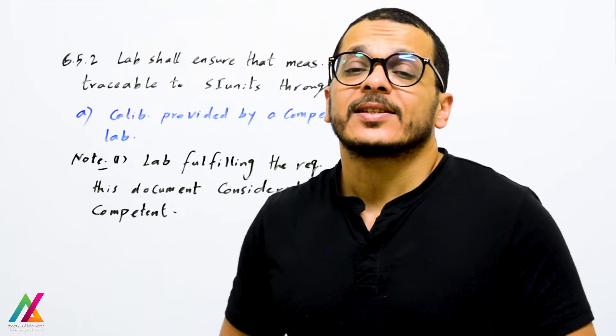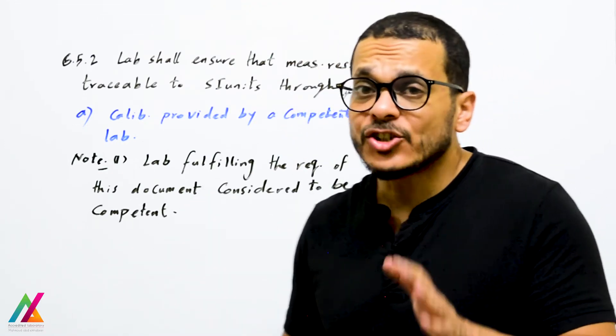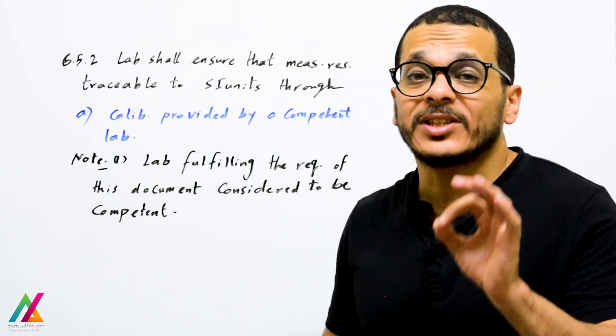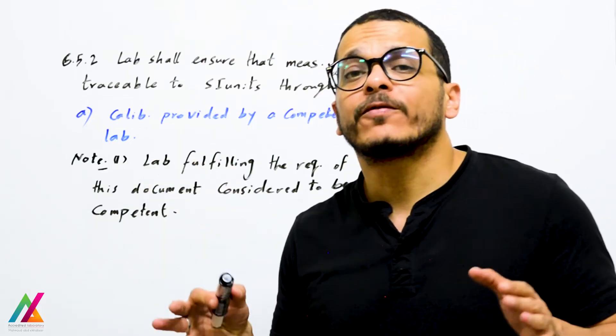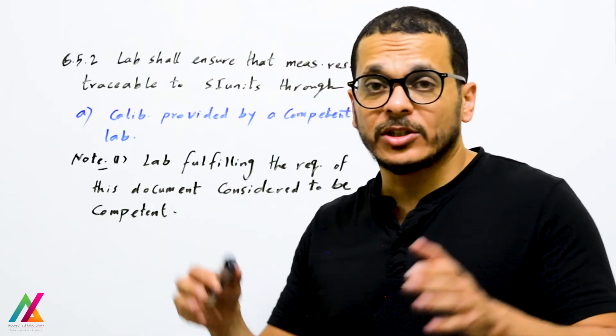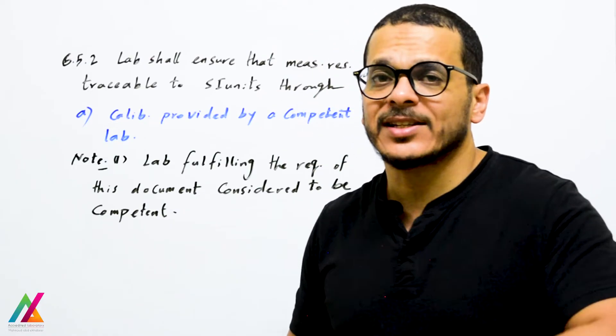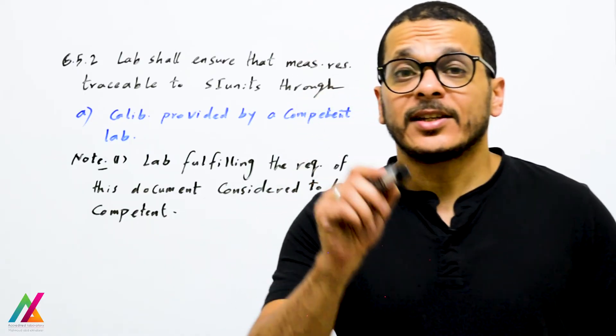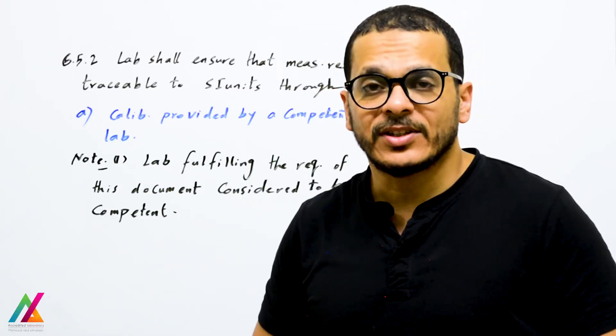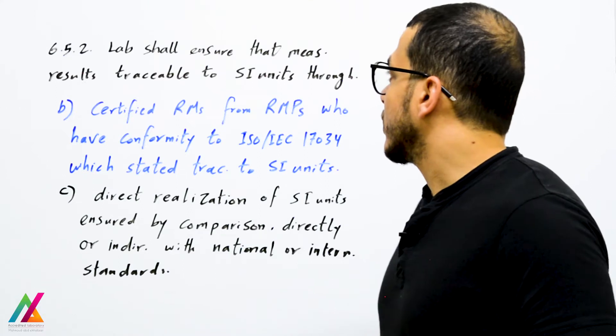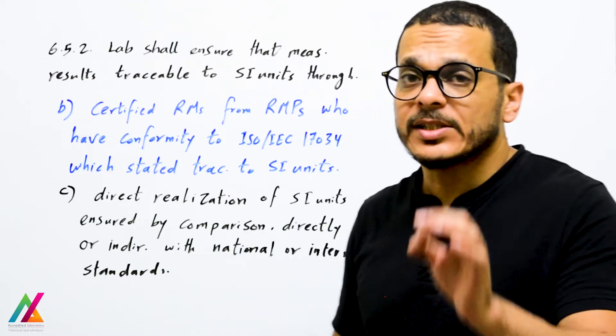The lab shall ensure that measurement results are traceable to SI units. First, calibration shall be provided by a competent calibration lab. Note 1 states that a lab fulfilling the requirements of ISO/IEC 17025:2017 is considered competent — so this lab shall be certified according to ISO/IEC 17025:2017.